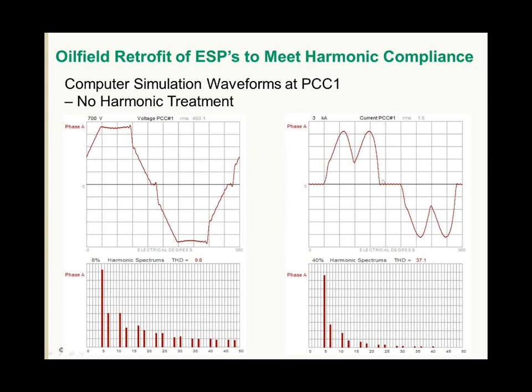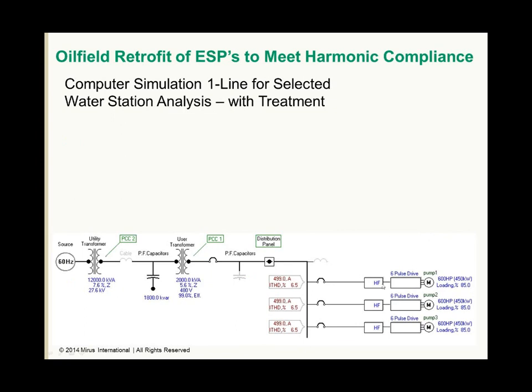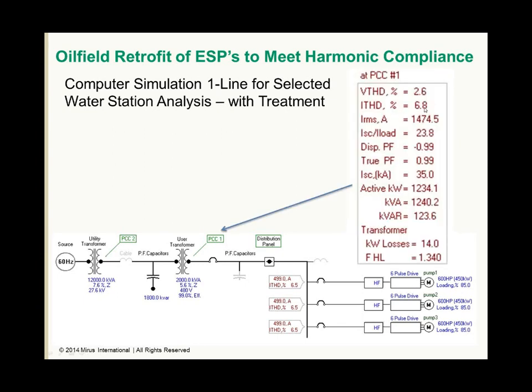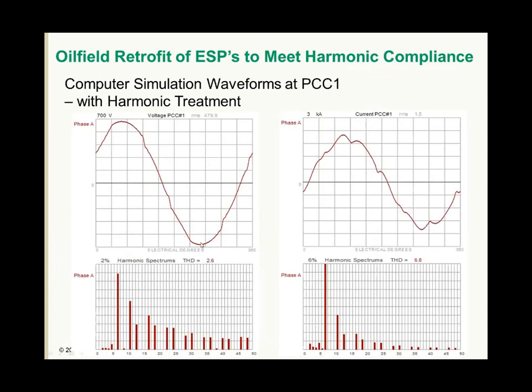And here's our input current, typical double humps, and the typical harmonics, the 5th and 7th, typical of a 6-pulse variable speed drive. And then we ran the simulation with passive harmonic filters applied ahead of the drives. Now we got current distortion down to 6.8%, and the voltage distortion dropped down to 2.6%. You can see our voltage looks much more sinusoidal, and current as well. There's residual harmonics. You can see there's a scale at 6%, so there's a bit of 7th, 11th residual harmonics, but overall much improved performance.